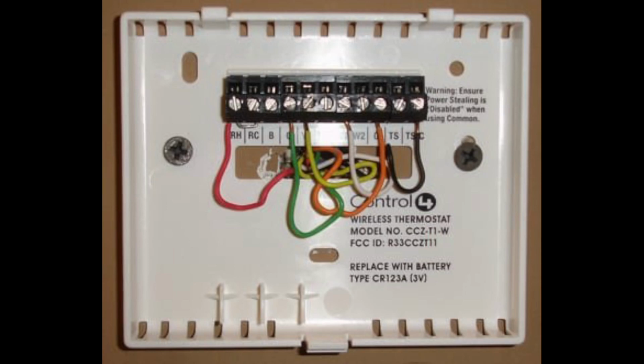And let me explain the difference. If you notice, everything is color-coded as well. Red is for power. And if you notice, if you see where it says RH and RC, this is the jumper that has to be in play. If you put this in there and that jumper falls out, this thermostat will not work. It has to sufficiently jump over from RH to RC.